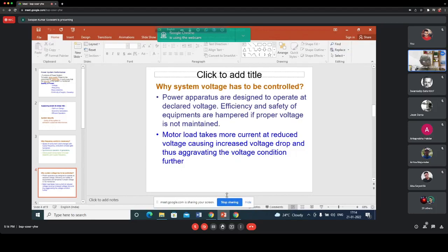As a result of the increased current drawn by the motor, there will be increased voltage drop. So already the voltage was less than normal. Now, because of the increased voltage drop, the voltage at the consumer end will decrease further. At the reduced voltage, again the load current will increase because the motor load will try to maintain constant power. So it will again draw more current. At the increased current, again there will be more voltage drop. So if this process continues, then what will happen? Voltage will go on decreasing, and a point will come when the voltage at the terminal of the node will collapse.